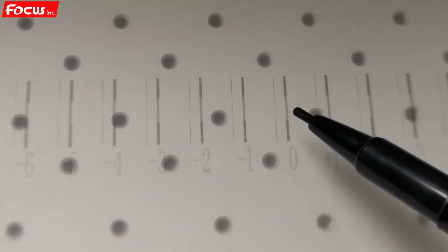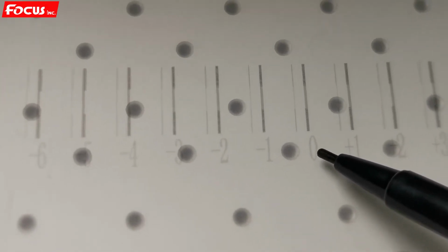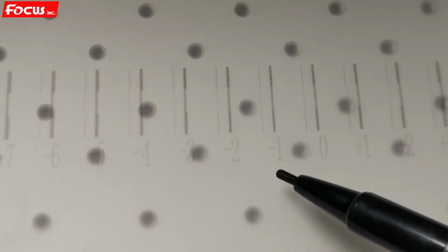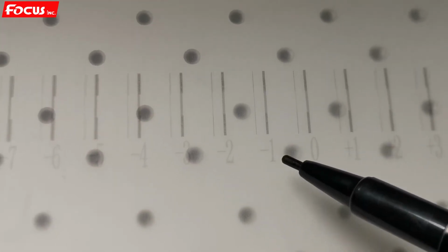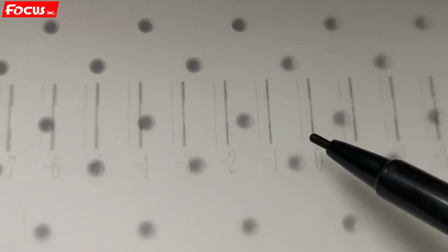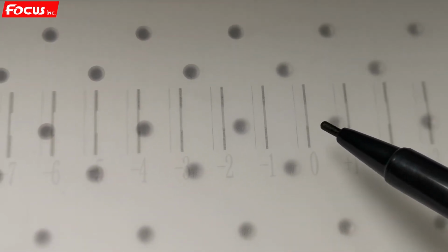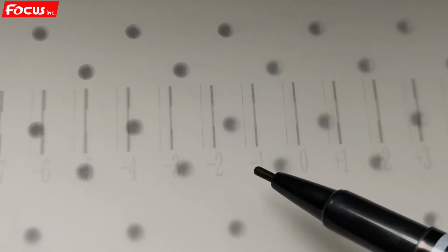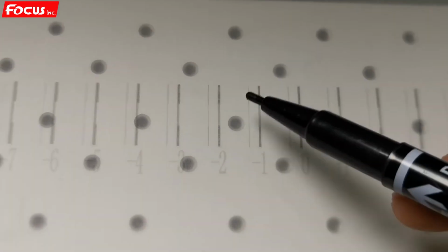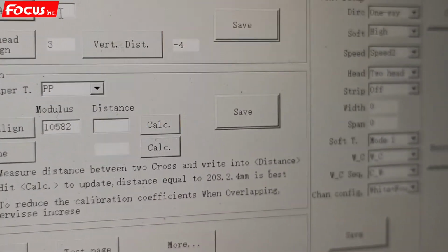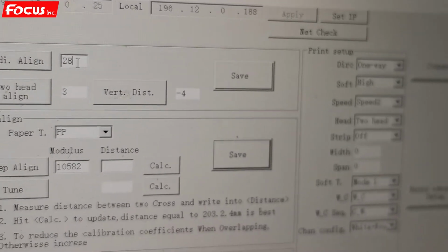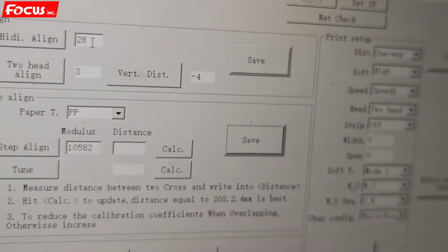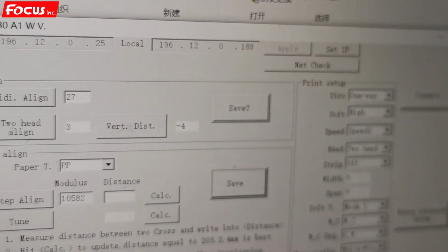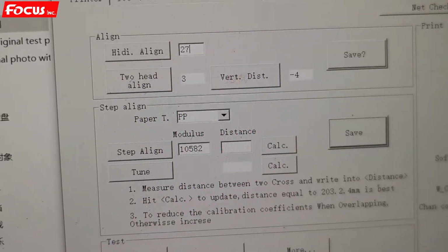So for example, this one, 0 is not the best. The -1 is the best. Anyway, we must be sure that after alignment, the 0 line is the best without any overlap for bidirection selection. So by this way, we put -1 to the number. Just remember that the -1 line is the best. Then we go to the software, and right now the number is 28. So 28 -1 will be 27. So we put 27 in the software.